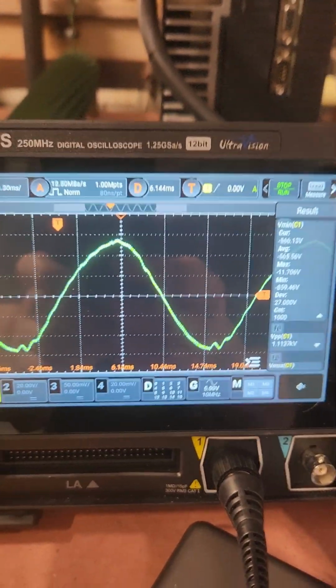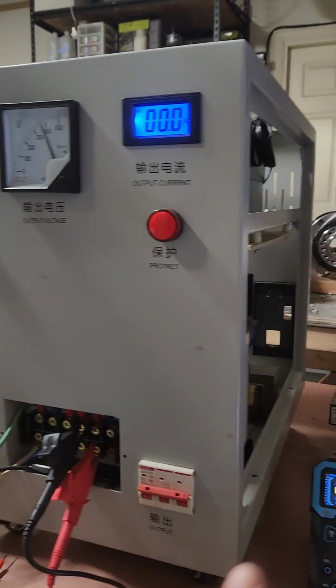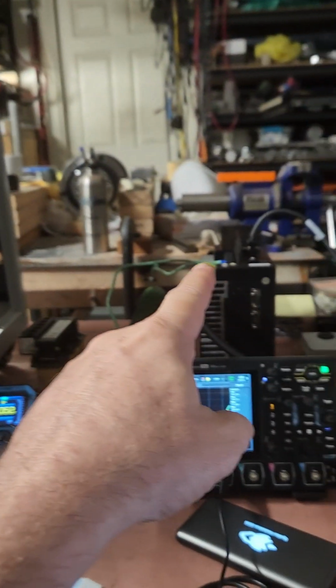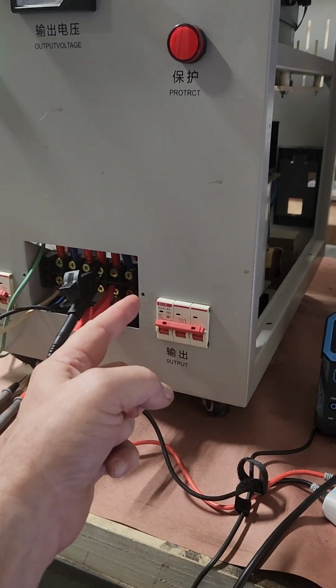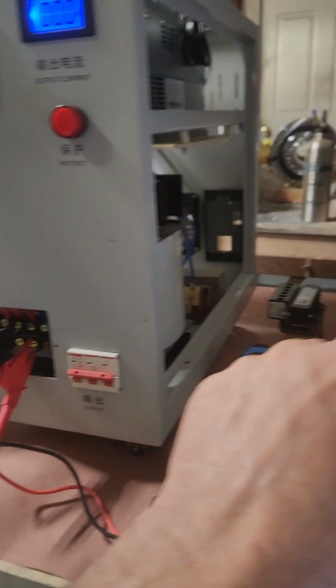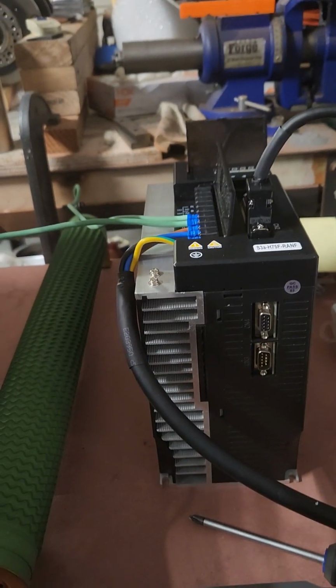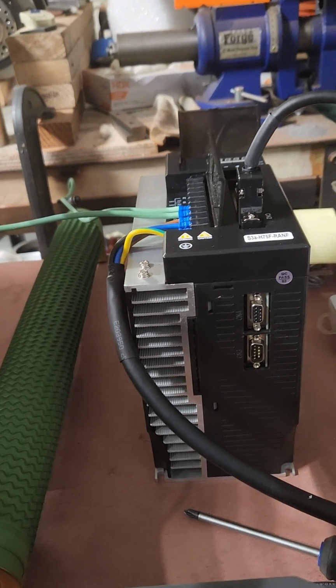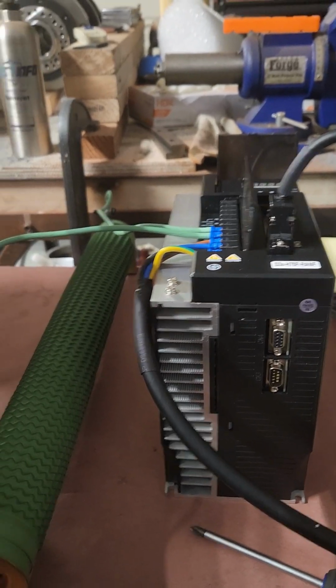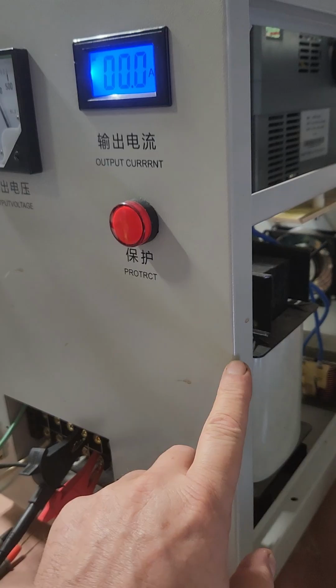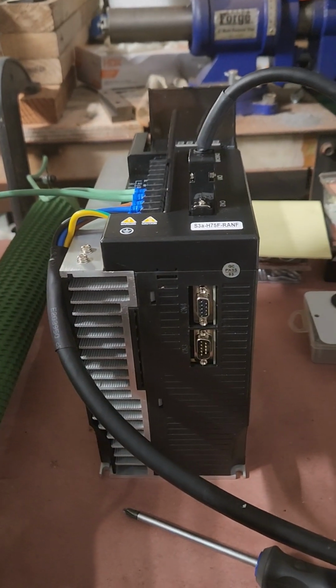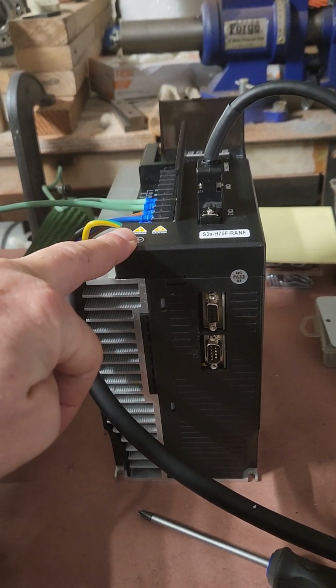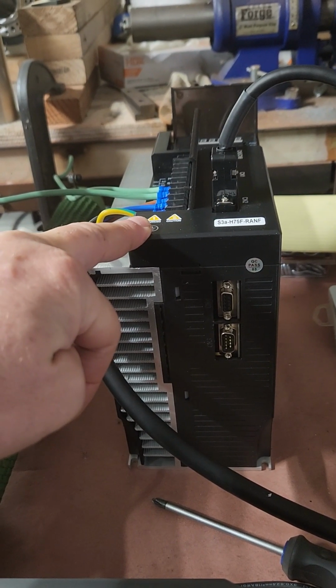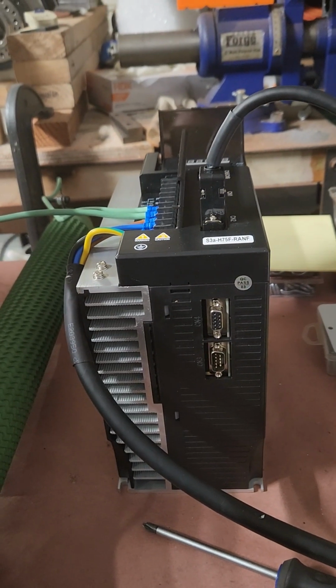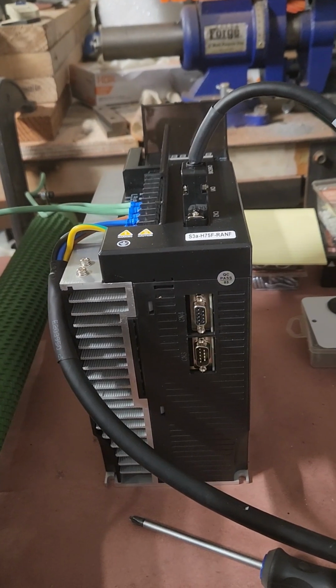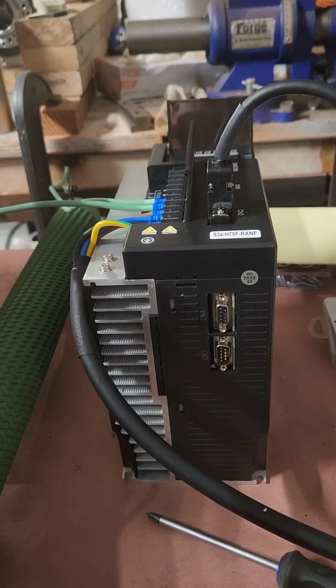Now what I don't know is do I just start this up in the state it is now and just put that directly there in the drive, or do I need to have it connected and start this from the control panel so the voltage slowly grows to provide power to the drive? Because the drive has the capacitors, right? And the capacitors, when they're discharged, they're like a short circuit. So putting 360 volts into a dead short will drive a high current in this. It has protection, but I don't know. On the other side, what I'm thinking, maybe this has a soft start. So usually when you charge a high capacitor bank, you have a series resistor, power resistor, and the voltage goes through that resistor to charge the capacitor, and when you reach a threshold you shunt that resistor with a relay so it goes directly. So if that's there, then I don't have this surge problem.